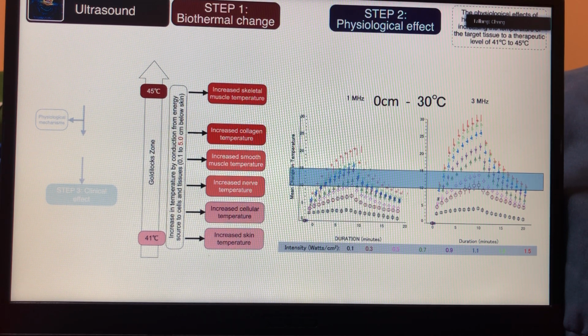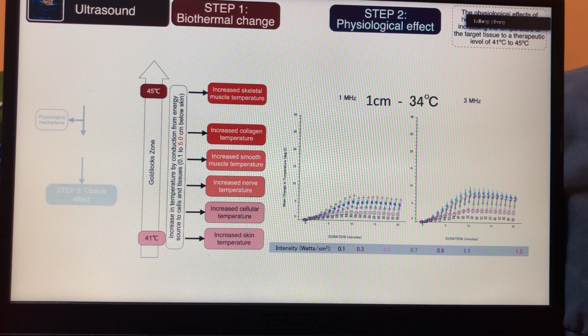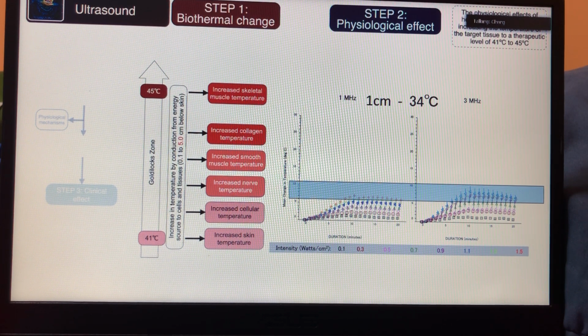So if you pass this, let's say at 0 cm, that means energy is not too much, not too little. Then let's look at below 1 cm. Try to remember, 1 megahertz is 0.5 to 1.3, and 3 megahertz 0.3 to 0.5. Let's go to the next one here. So at 1 cm, you can see that for 3 megahertz, you are getting in the physiological range. The therapy Goldilocks zone is there, but those are the intensities that we already ruled out, because they're too high for the skin. 0.3 to 0.5 is not in that range.